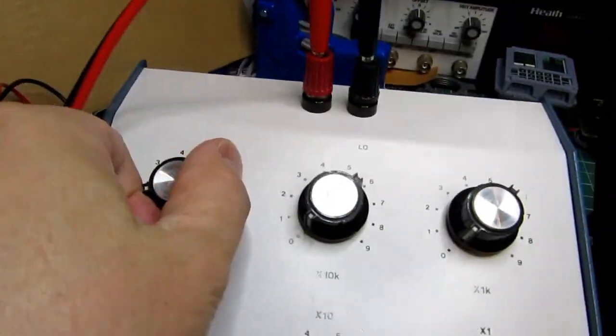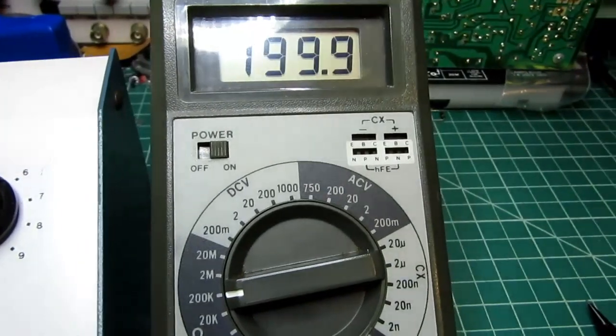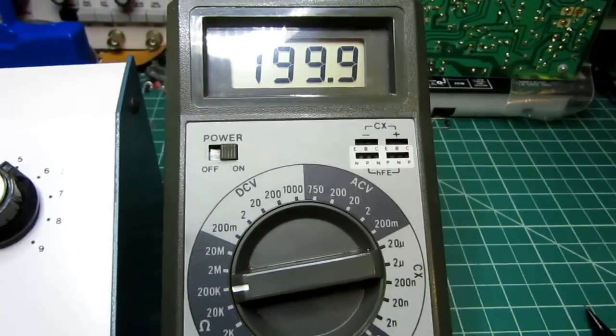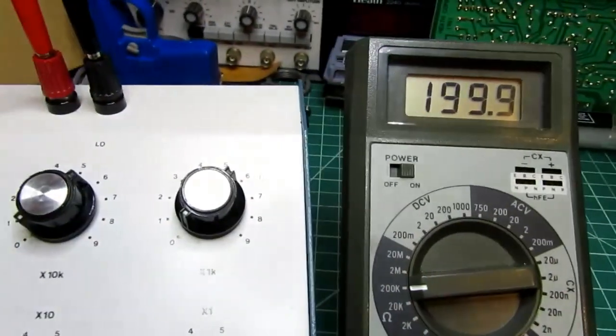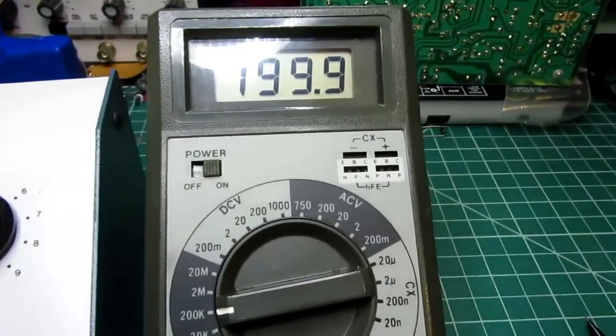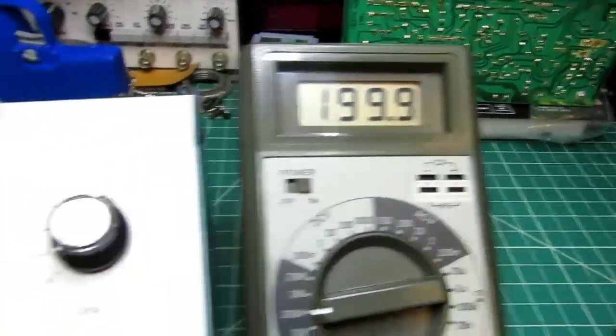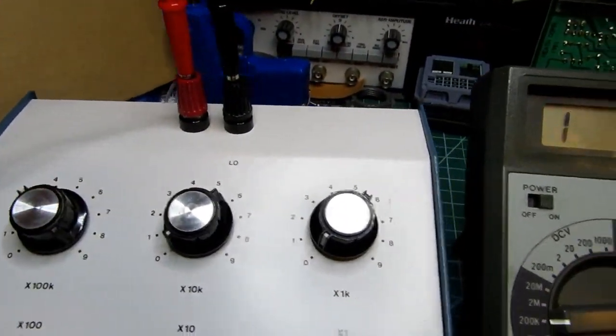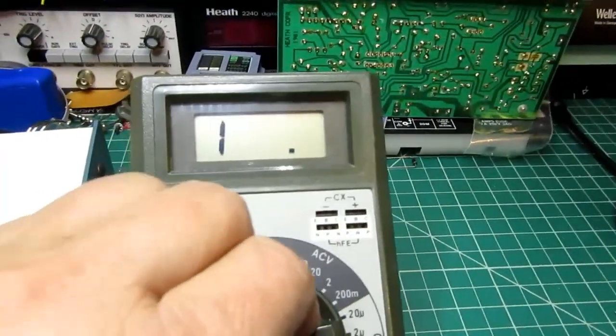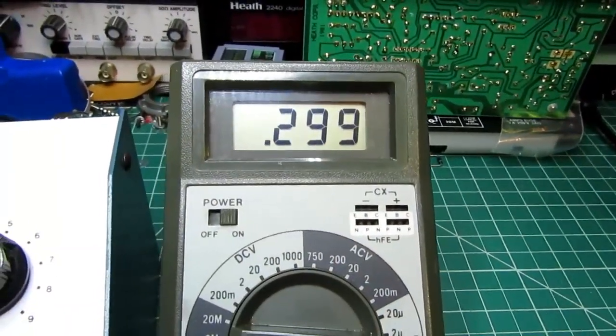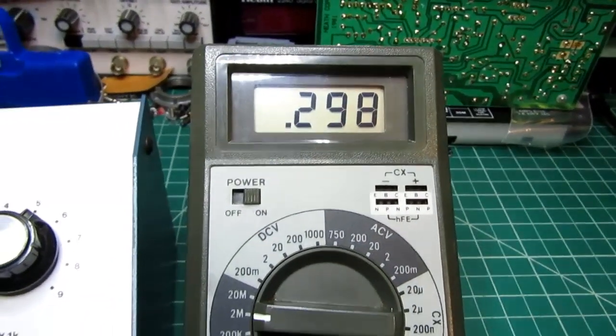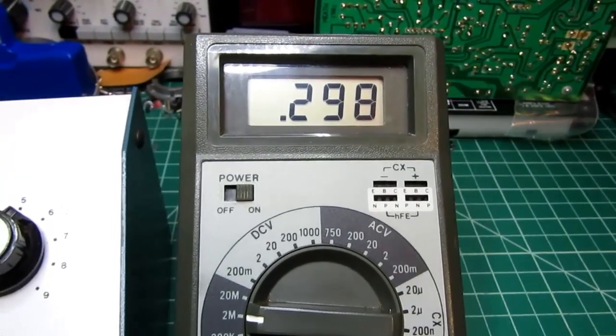If I go to 200 here, we're going to overrange. It's actually right on the hairy edge. It's reading slightly low, a little bit of tolerance in this, so it actually doesn't overrange, but it's right on the hairy edge of doing so. If I go to 300K here, it definitely overranges. I have to go to the 2 meg range, and I'm reading really close to 300K there.